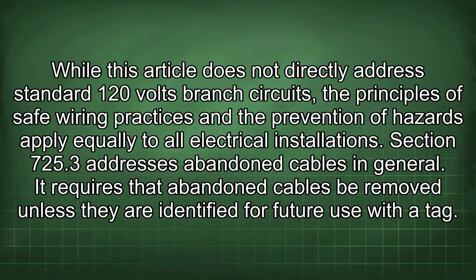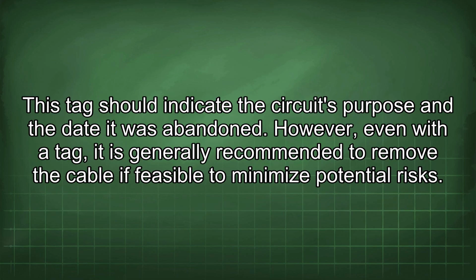While this article does not directly address standard 120-volt branch circuits, the principles of safe wiring practices and the prevention of hazards apply equally to all electrical installations. Section 725.3 addresses abandoned cables in general. It requires that abandoned cables be removed unless they are identified for future use with a tag. This tag should indicate the circuit's purpose and the date it was abandoned.